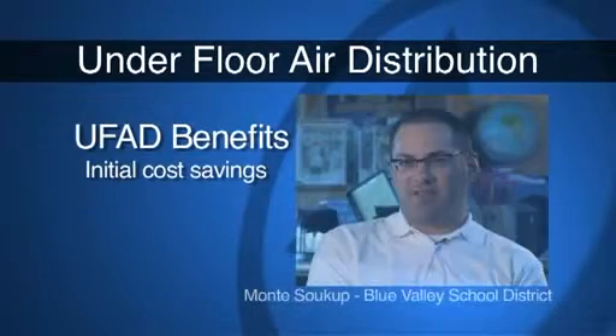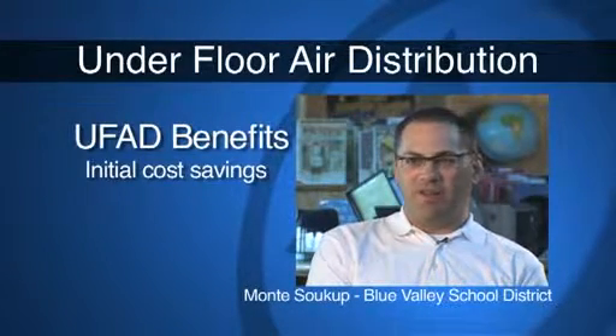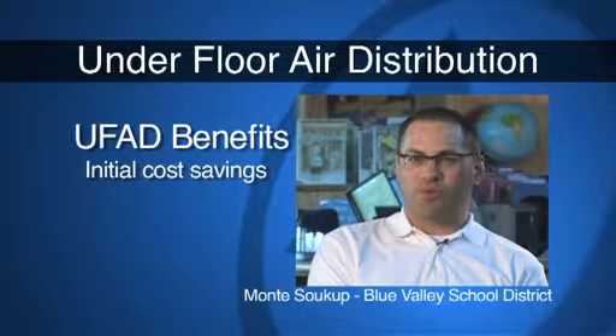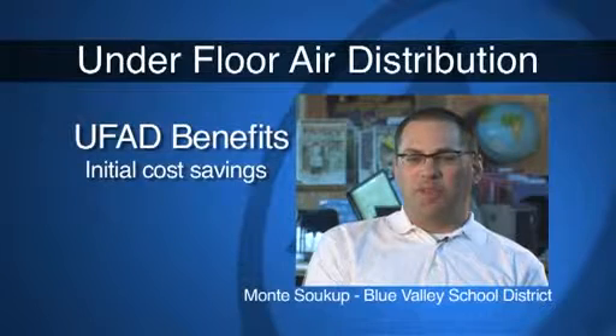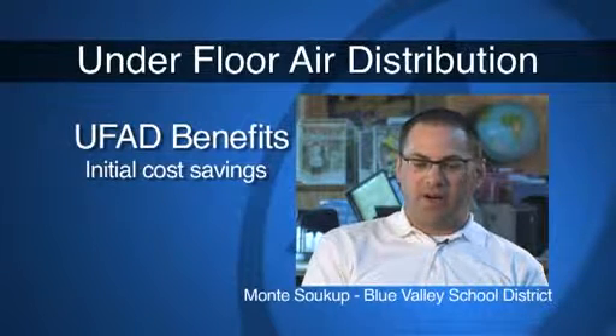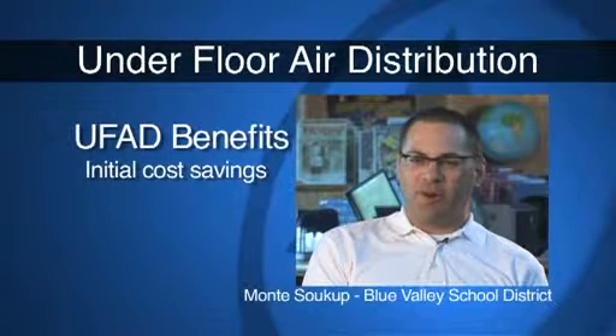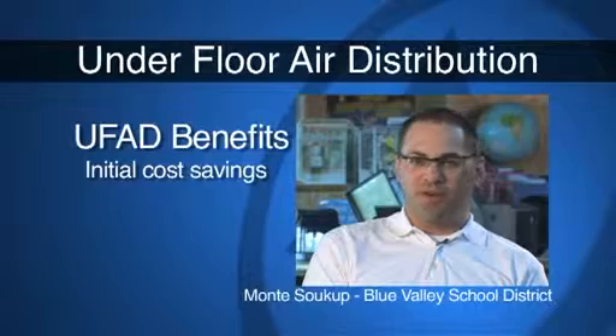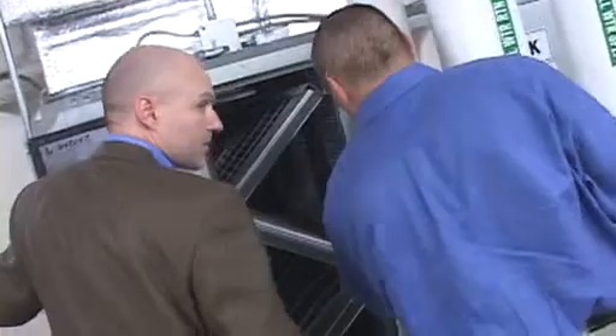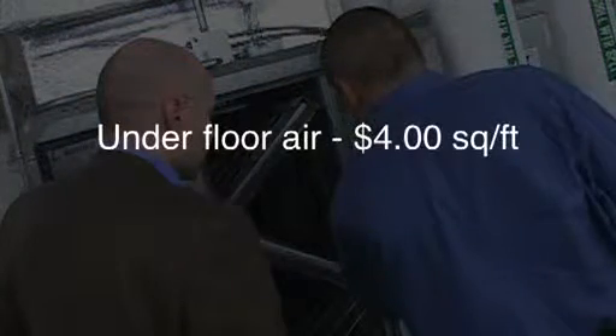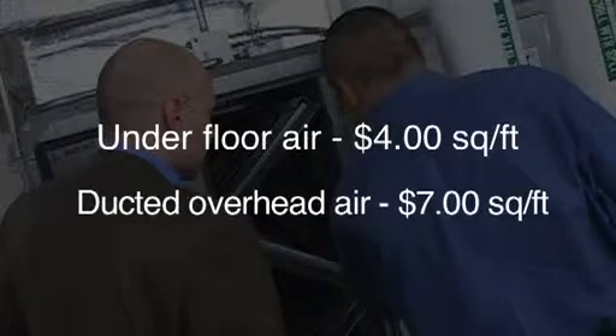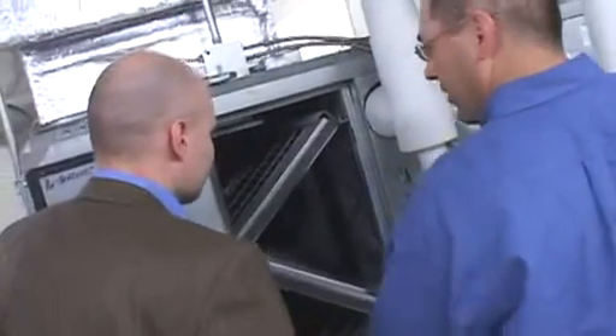Now let's explore the initial cost savings to be gained with underfloor from the equipment and installation perspectives. Probably one of the biggest savings is fan horsepower, because most of your energy in your system is lost in the delivery of the actual air. It's a fan motor. So with a displacement system and the underfloor air, we have a lower plenum pressure, so it takes less fan energy to deliver the air. The initial cost savings when installing underfloor air are benefits important to every job we plan. When we exclude the capital cost of the equipment, we've experienced underfloor air numbers of $4 per square foot. We've all seen ducted overhead systems come in at $7 per square foot and more. These savings come from a number of factors.